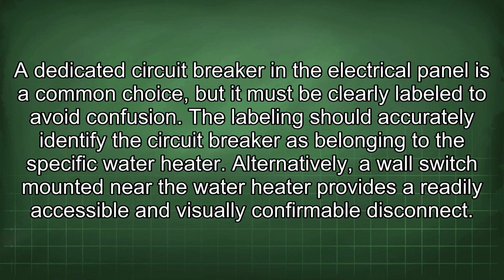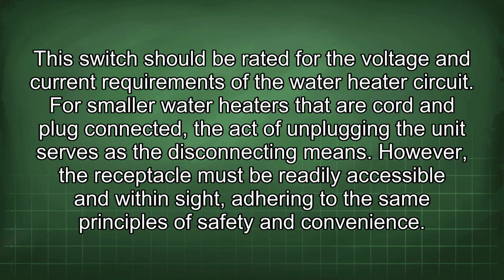A dedicated circuit breaker in the electrical panel is a common choice, but it must be clearly labeled to avoid confusion. The labeling should accurately identify the circuit breaker as belonging to the specific water heater. Alternatively, a wall switch mounted near the water heater provides a readily accessible and visually confirmable disconnect. The switch should be rated for the voltage and current requirements of the water heater circuit. For smaller water heaters that are cord and plug connected, the act of unplugging the unit serves as the disconnecting means. However, the receptacle must be readily accessible and within sight, adhering to the same principles of safety and convenience.